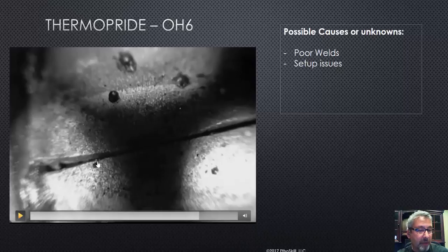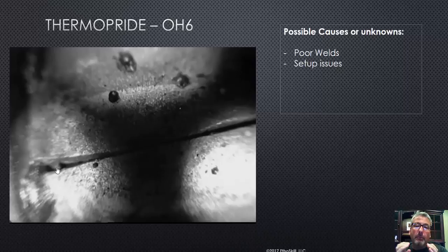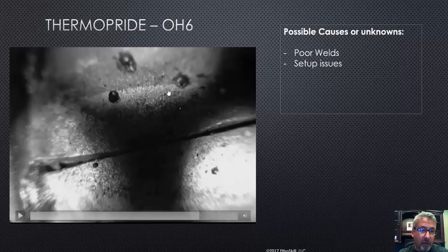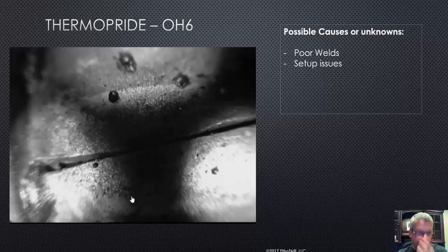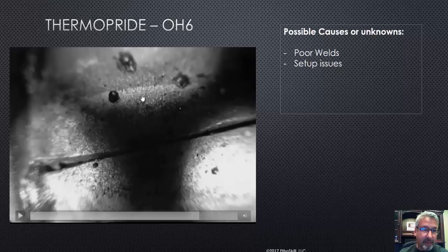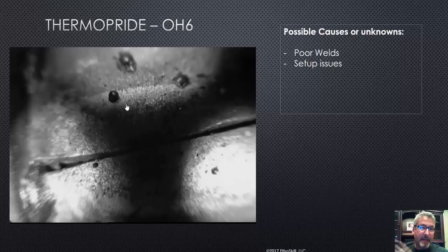Another tricky little problem to find. So either we have a lack of weld here or where they brought the two pieces of metal together, it started to open up. You know, you could see a weld splatter here. So I don't know what's going on there. But as you see here, you see here, I'm guessing this weld splatter is coming from this joint and then all the other joints. I mean, when you're welding, if you've ever been around welding, man, there's stuff flying everywhere. A little weld splatter is not a big deal, especially on a heat exchanger. This thing is not designed for its cosmetic purpose.